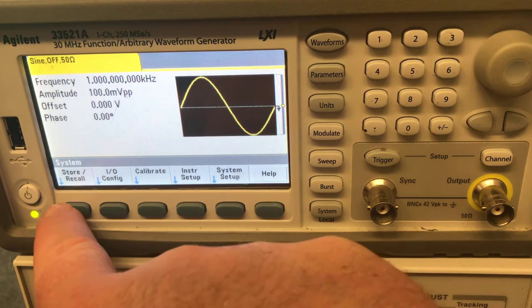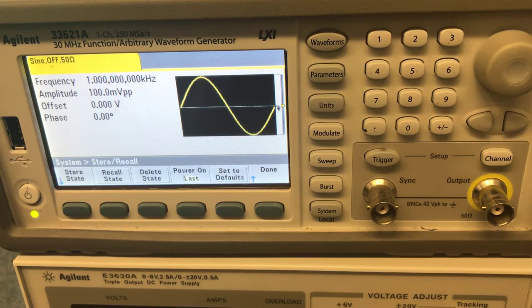My first advice is that immediately after you turn it on, push the system button, go over to store recall, and then say set to defaults. Because who knows, the person who used this before you, how they left it set up. You want to clear all of those settings and make sure that they're down to the initial configuration that you expect them to be. That's a good thing to do every single time that you use this piece of equipment.